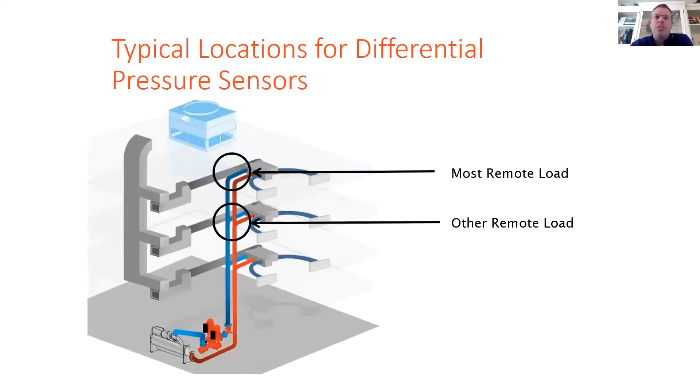So a second option that is sometimes used is mounting the sensor two-thirds of the way down the piping system, and the minimum head set point is now going to be the remaining one-third of the piping, along with the remote loads, control valve, strainer, coil, balancing valve, et cetera. So this minimum differential pressure set point is going to be a little bit higher, but it's going to still allow decent energy savings.